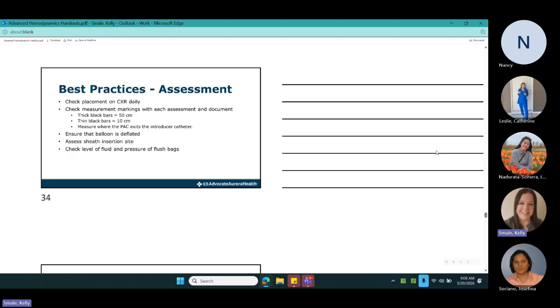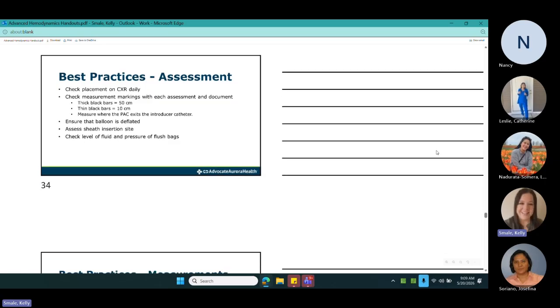If you ever have any issues, generally we don't have these issues with CV swans. It's mainly cardiology swans because cardiology swans, for some reason, do not lock. I don't know why they don't lock, but they don't. But the CV ones have 2 locks on them, so we generally don't have problems with them coming back or migrating further in. If your waveform is bad and you think you need a chest X-ray, order a chest X-ray and just notify AIP that my line is moved or there's an issue with it, because sometimes they will kink. They do hold a lot of slack inside the patient, so they can move that way.